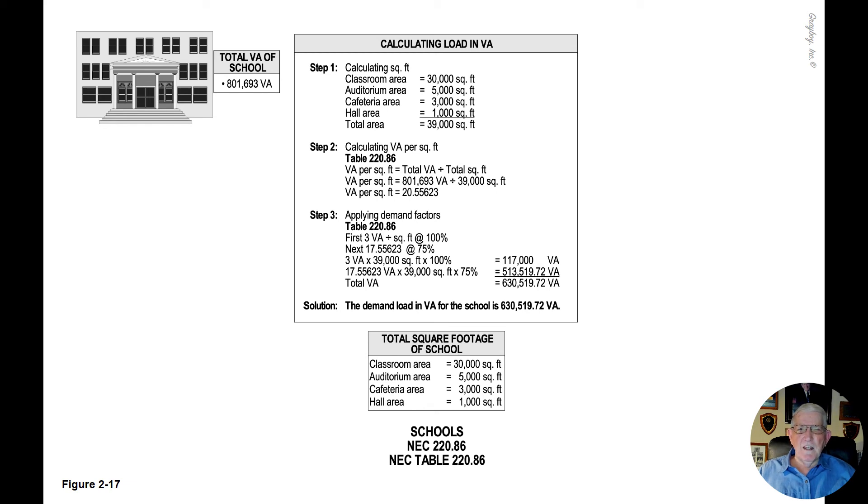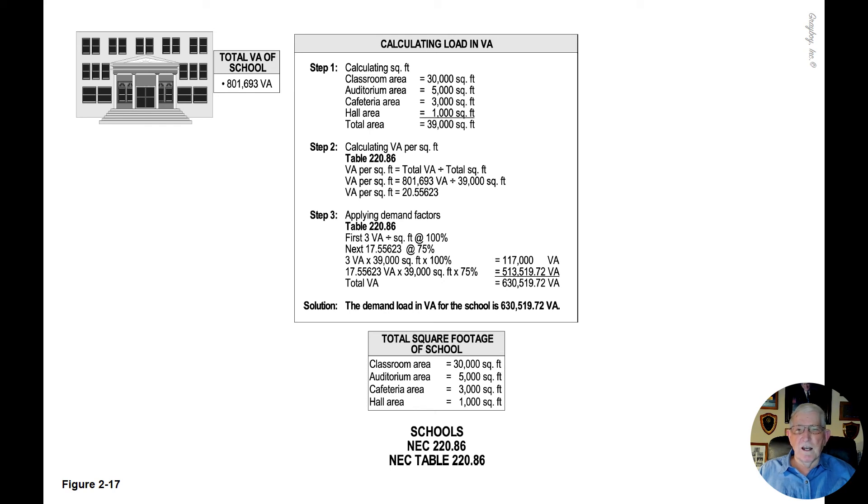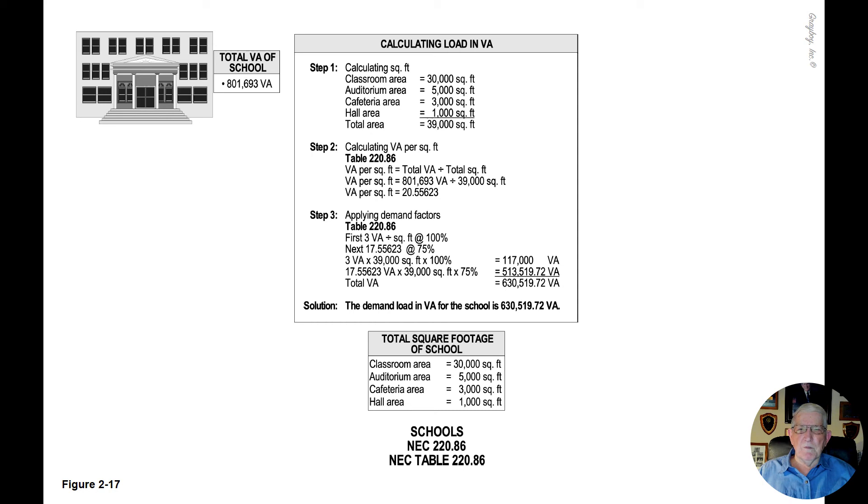So the VA per square foot is 801,693 VA divided by 39,000 square foot. So the total VA per square foot is 20.55623.